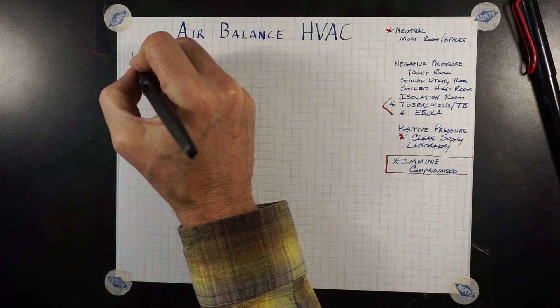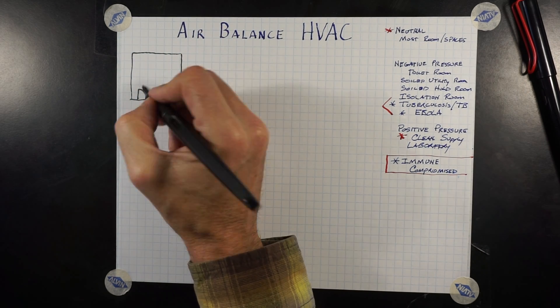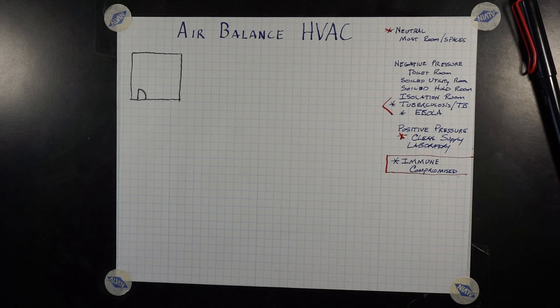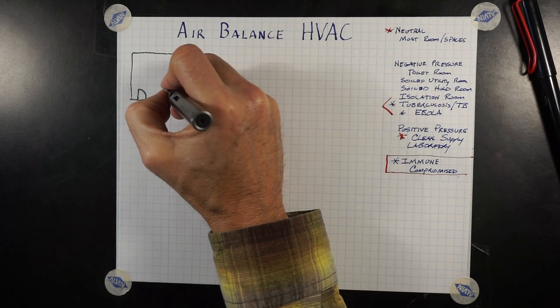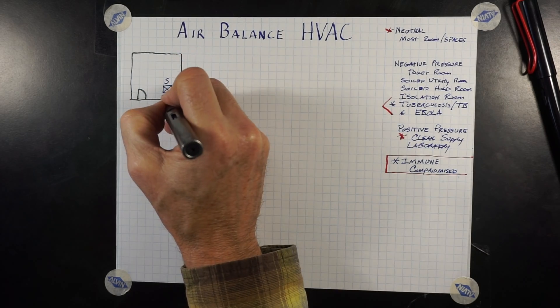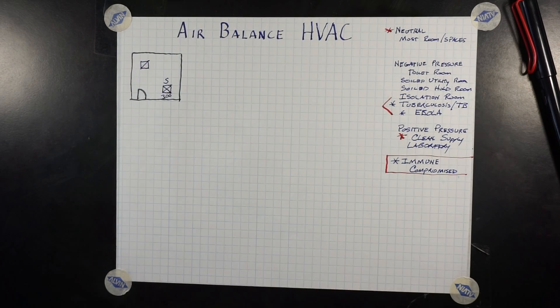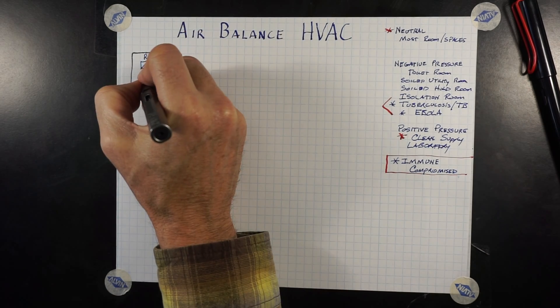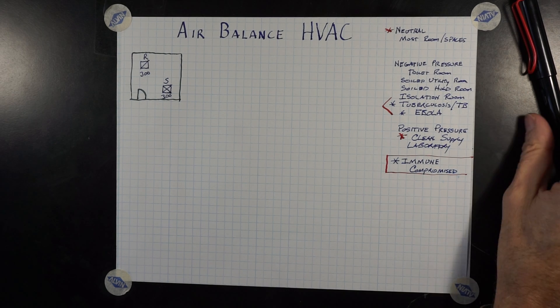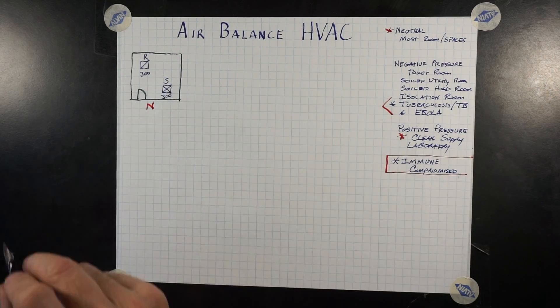Let's draw a room. And in that room, we have a supply duct shown here with an S and an X through it of 300 cubic feet per minute of air. Let's draw a return air duct. Typically it's one line through it, drawn here. Let's put an R here for return, and it's 300 cubic feet of air leaving the room. So the amount of air going in and the amount of air coming out are the same. That room is considered neutral.